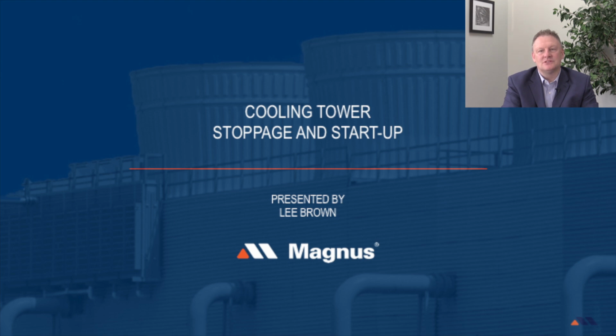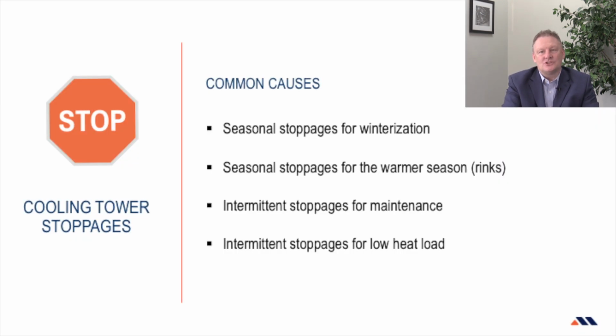In a perfect world, cooling systems would continuously operate with no stoppages. Ideally, the exposed water surfaces would always be in contact with flowing water, which would make protecting the metal surfaces and controlling microbiological growth much easier. Unfortunately, this is not the case, as most comfort cooling systems operate seasonally and will undergo winterization, where equipment is emptied and the systems can be left with sections that are partially submerged with stagnant water.